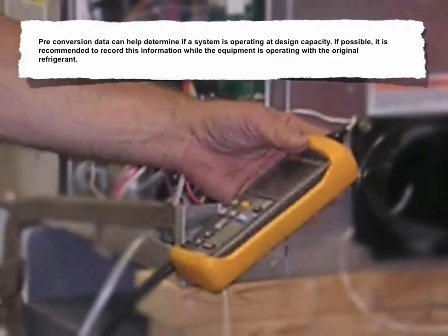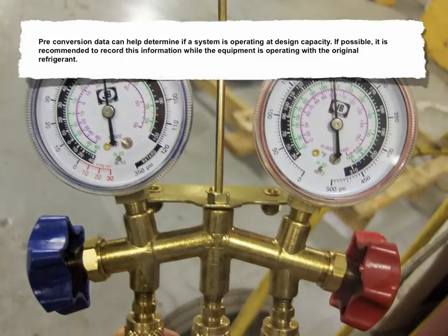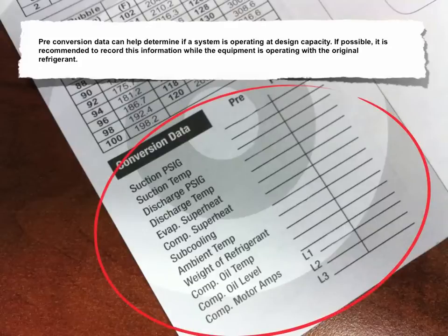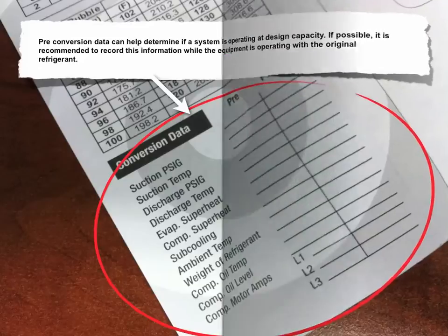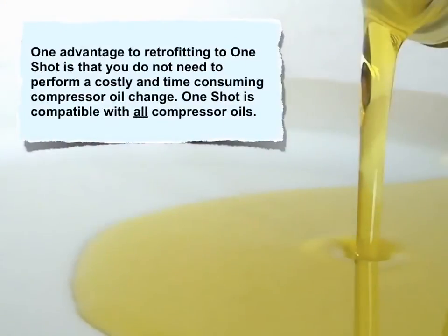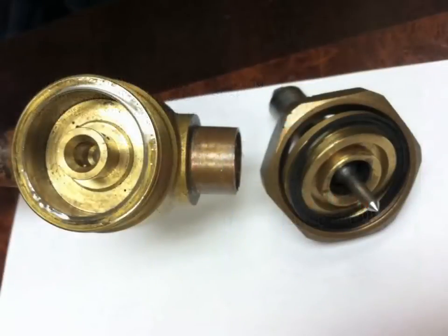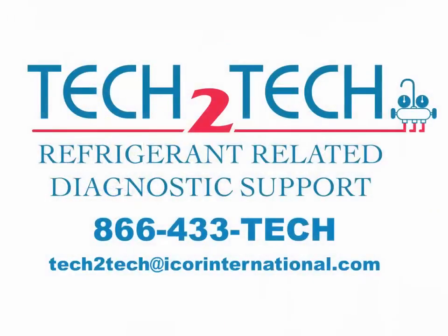Pre-conversion data can help determine if a system is operating at design capacity. If possible, it's recommended to record this information while the equipment is operating with the original refrigerant. A pre-conversion data form can provide helpful information and can be used as a reference after the conversion. One advantage to retrofitting to One Shot is that you don't need to perform a costly and time-consuming compressor oil change, as One Shot is compatible with all compressor oils. It's important to know that you'll need to replace critical elastomers, rubber seals, and gaskets on components common to larger systems.